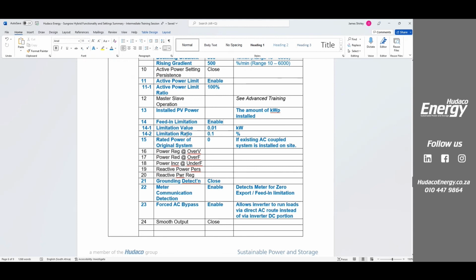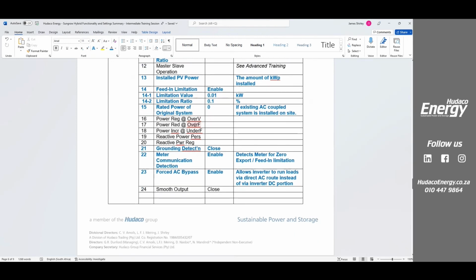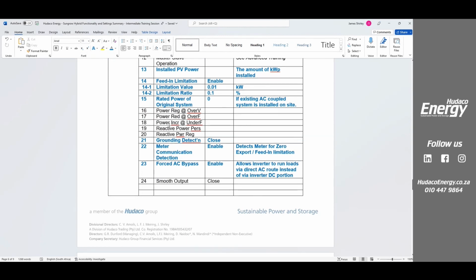Or we could do it as a ratio. In other words, if you're producing 5 kilowatts of PV, let's say we used 50%, it would only allow us to feed in 2.5 kilowatts. This is back to grid, by the way. So we call this zero export. Zero export is generally the term we use in South Africa, because for us, it's either on or off. But in other areas in the world, you can actually feed in a certain kilowatt amount. That's why they call it limitation on the feed-in. Then we've got a whole lot of settings about power regulation, over voltage, over frequency, under frequency, and so on.